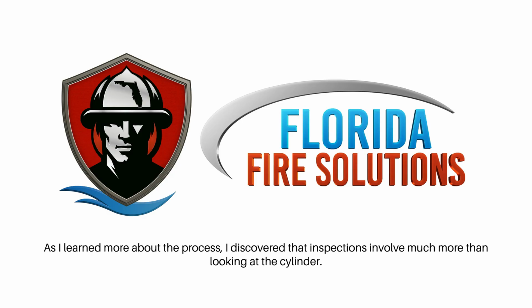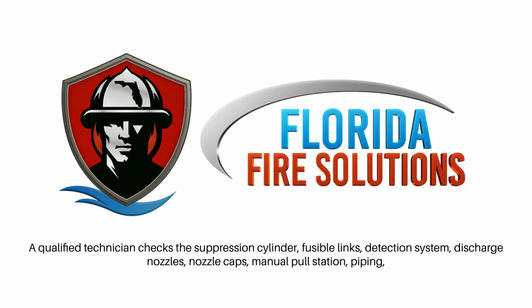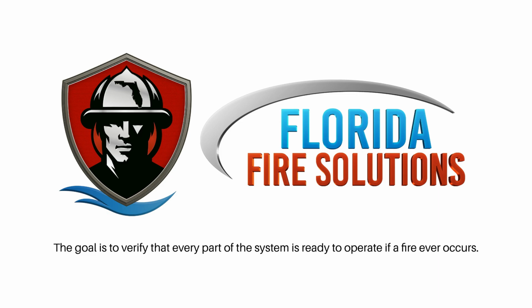As I learned more about the process, I discovered that inspections involve much more than looking at the cylinder. A qualified technician checks the suppression cylinder, fusible links, detection system, discharge nozzles, nozzle caps, manual pull station, piping, and the operation of fuel and electrical shutoffs where required. The goal is to verify that every part of the system is ready to operate if a fire ever occurs.